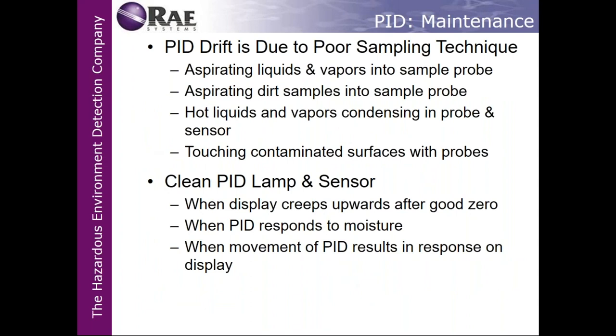PID drift is due to poor sampling techniques. Sometimes people will suck up liquids and vapors in the probe. This happens usually, especially in the fall or during the wintertime. If you're outside doing investigations, like around creeks, ponds, or if you're on site, sometimes people lose their depth perception because it's getting dark, and they'll actually drown their PID. They'll put the tip in the water, or they'll accidentally hit it with the chemical, and that chemical stays in the filter and gives you a false positive. So touching contaminant surfaces with probes is very bad. If you do that, take the unit out of service and clean it with the cleaning solution that comes with your PID.